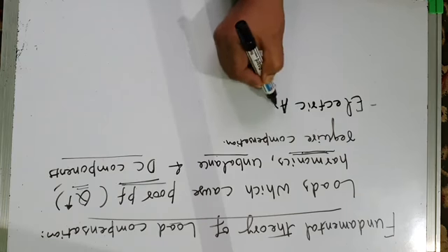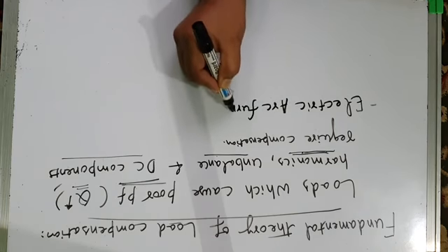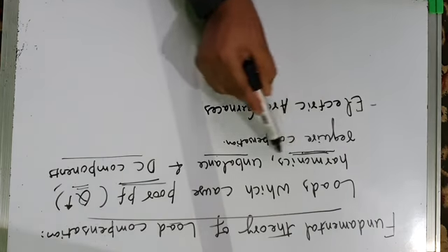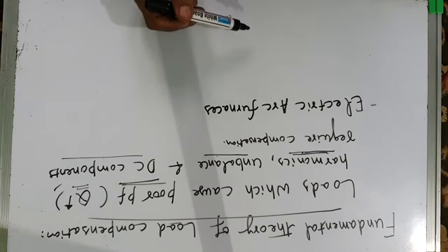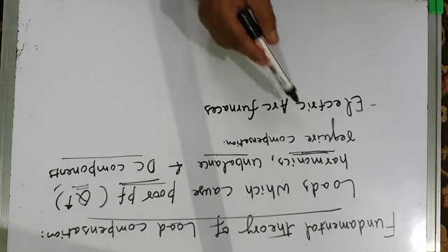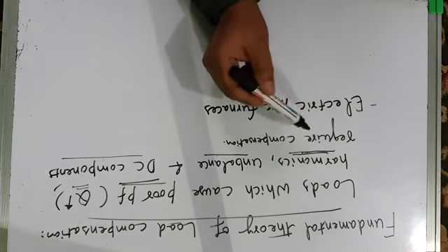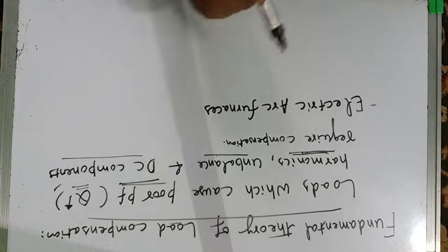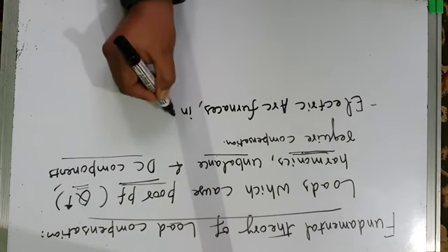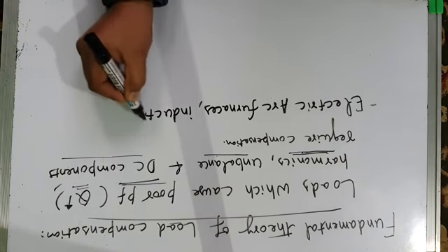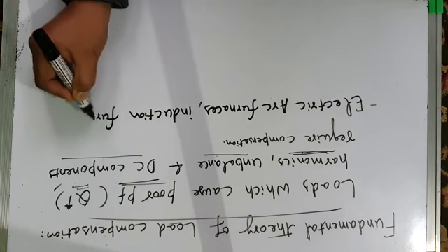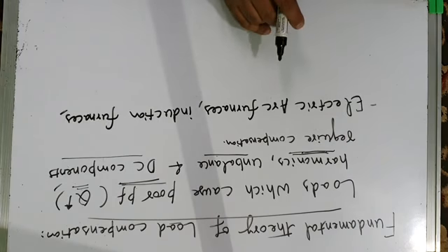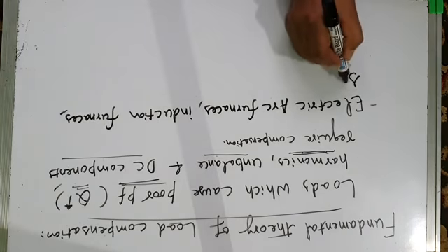Electric arc furnaces. Electric arc furnaces cause tremendous harmonics in the system because they inject large harmonics into the system, and they also result in poor power factor. Induction furnaces. Induction furnaces are also responsible for harmonic injection in the currents and hence voltages.